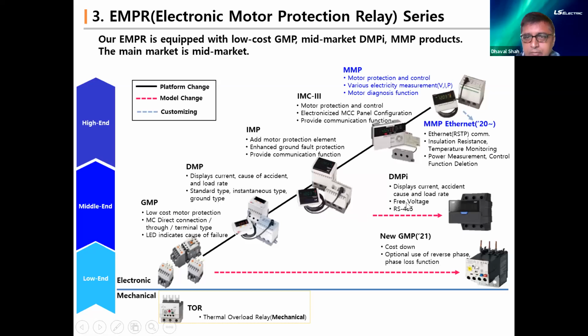There is also a new model, DMPi, which in addition will have RS485 communication. In IMP, in addition to the DMP, you get enhanced ground fault protection and communication functions. Then there is IMC, the Intelligent Motor Control Center. As the name suggests, you can configure the software and use various DMPs and IMPs on the various motors in one single software. And the last one is MMP, which in addition to current gives you voltage protection as well as power protection.